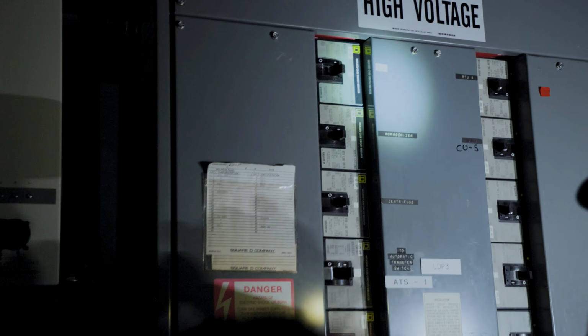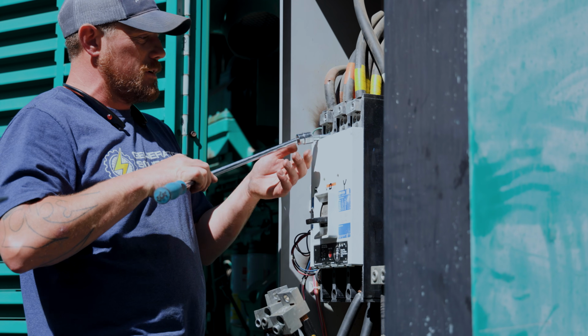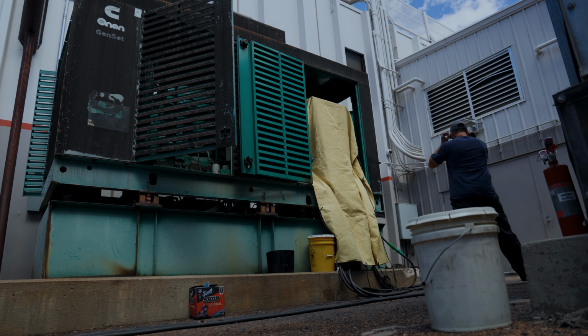Our technicians were able to troubleshoot the breaker that got flipped on the inside, get their building back online, repair the damage that was done to the unit, and then load bank it to ensure that there was nothing else that was going to go wrong in the event of an actual outage.